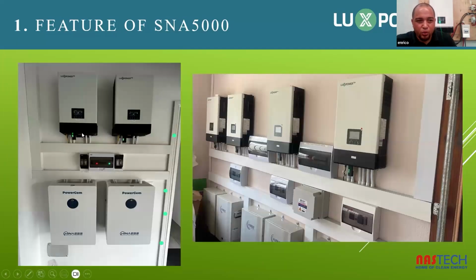Here they are. So all those protection boxes. This is your solar panel protection boxes, and these are your DC panel protection boxes. Your changeover switches. Your changeover switch is here on the side. Here you can see within this protection box, we have our indicator for Eskom, that Eskom is present or the grid is present. And as well, we have an indicator light that the inverters are working and functional. So this is your AC protection box.